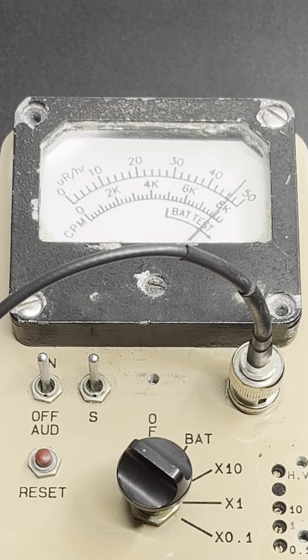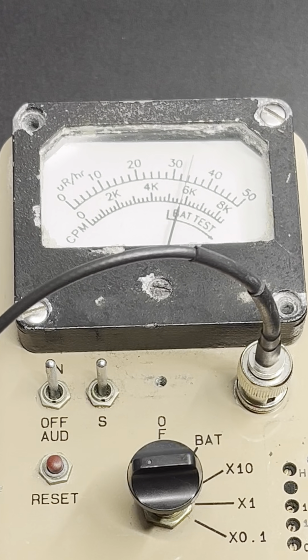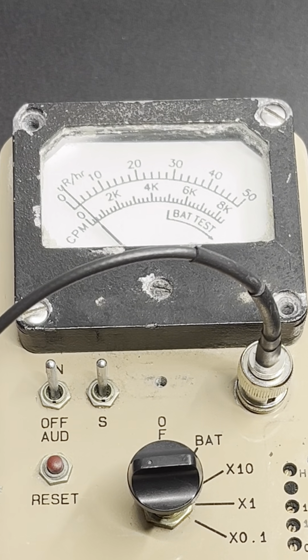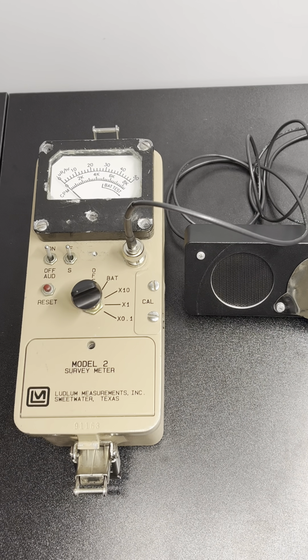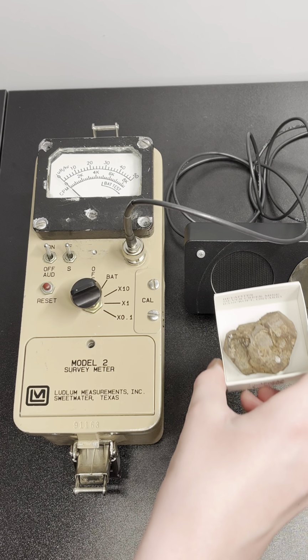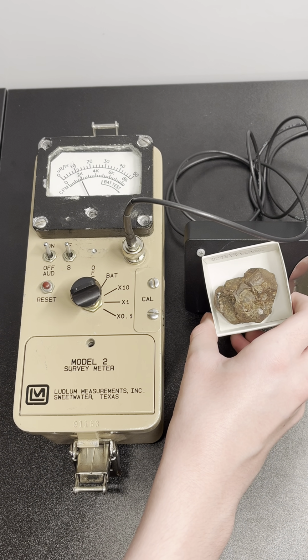reading is perfect. I then go to the next scale and do it all over again until I get to the last scale. And once that's done, I have a fully calibrated meter. Well, except for field calibration, which I can't really do without having a license for much better sources than I have on hand.